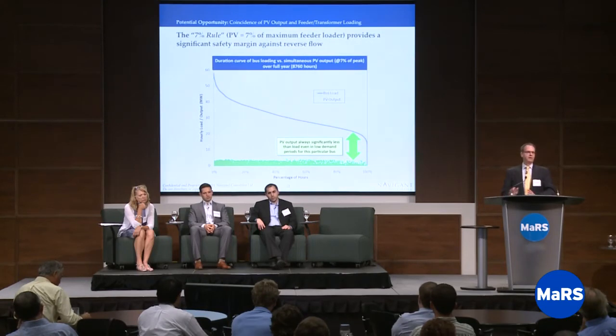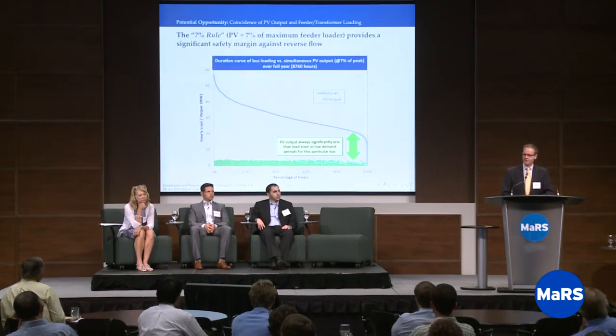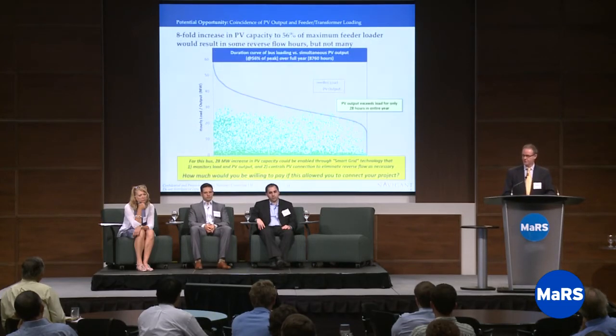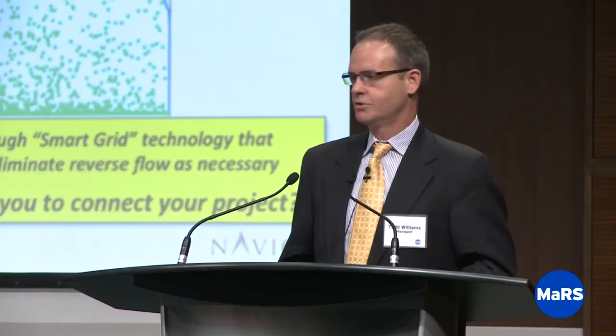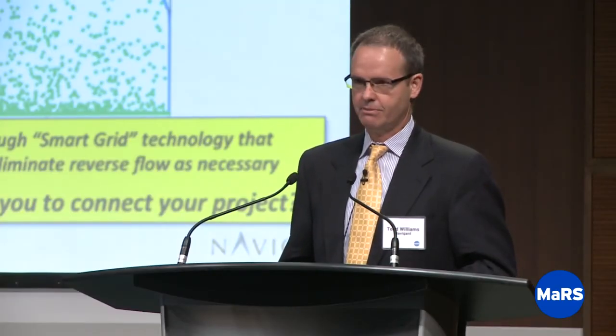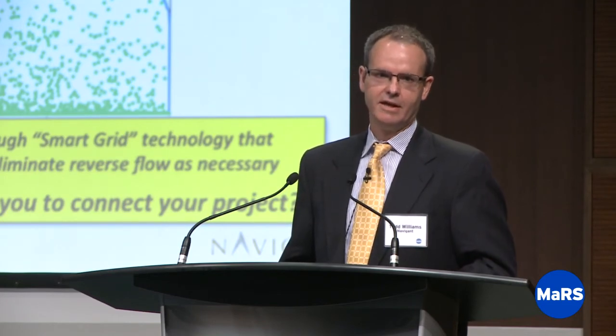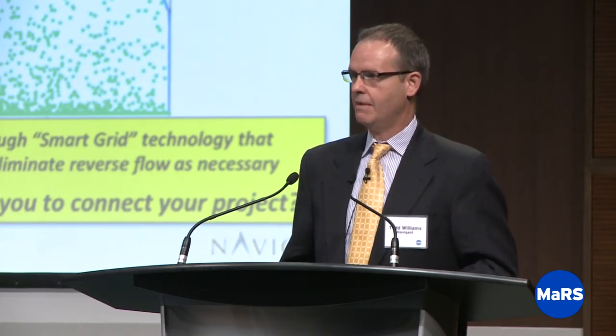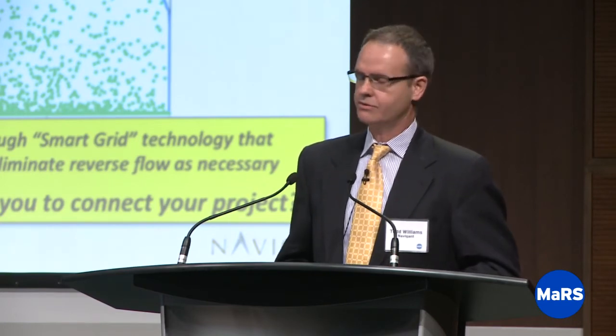What if, for example, I said, I don't want to be so conservative, I want to bump it up a little bit, and I said, I want to get 8 times as much. So let's have a rule of 56%. If we went to an 8-fold increase in output to 56% of the maximum feeder loading, it still doesn't exceed it very often. It does in 28 hours of the year. Those are the points to the right-hand side, just above the curve where the solar output is higher. Those are the hours when it would be backfeeding, if you will, or in a sense running the transformer in reverse.